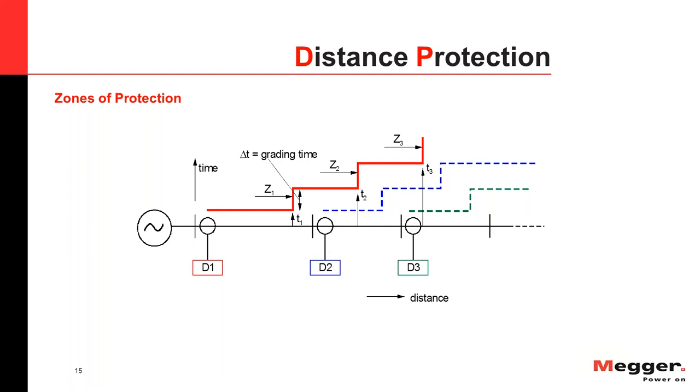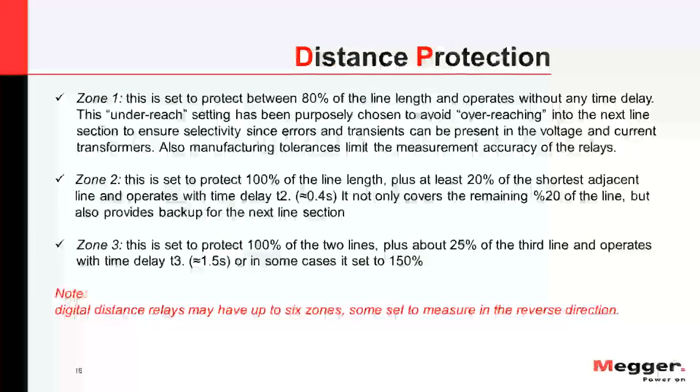And this is all coordinated by time, and there will be different time settings, and this calculation also has to be well coordinated with the other line protection, so there will not be a conflict or mistripping, or let's say false tripping, because of the time coordination.